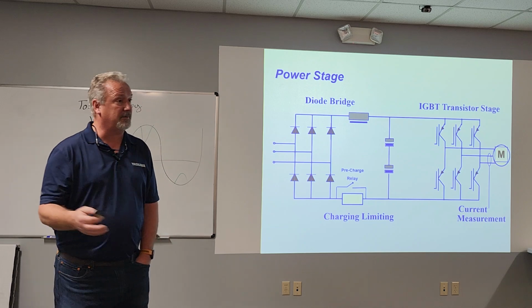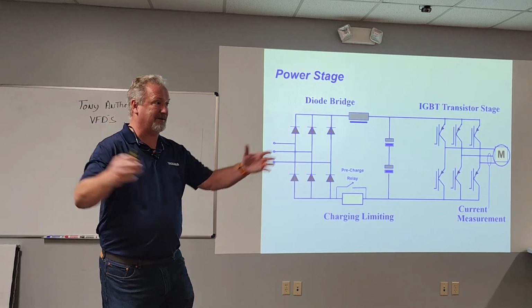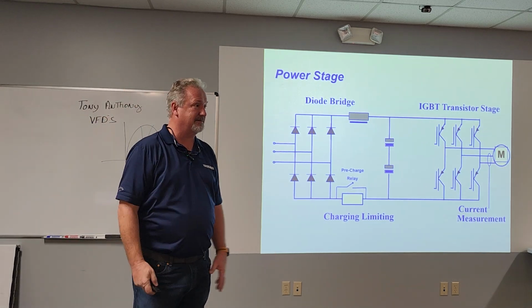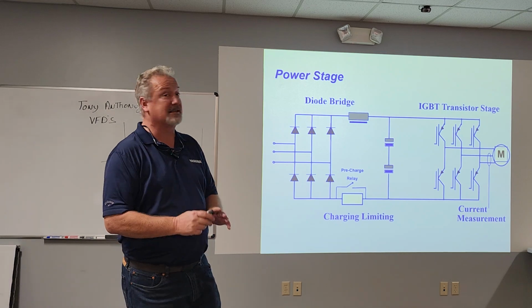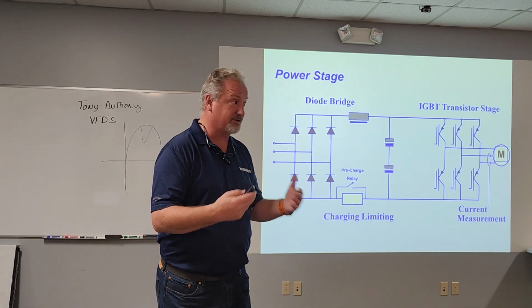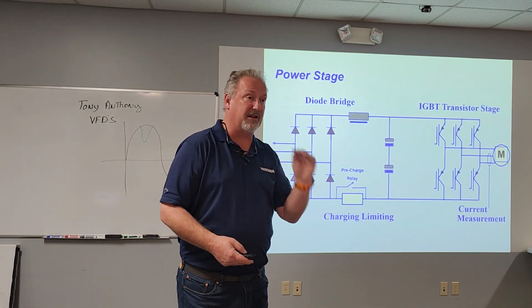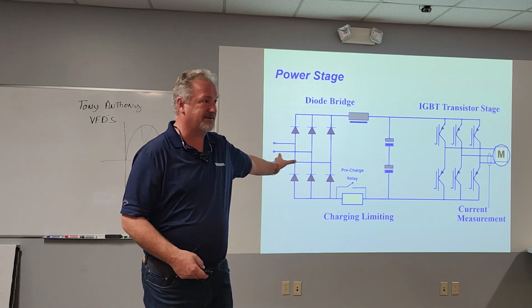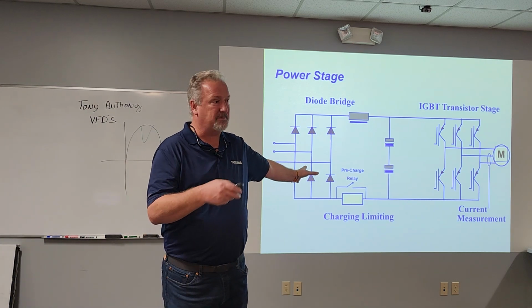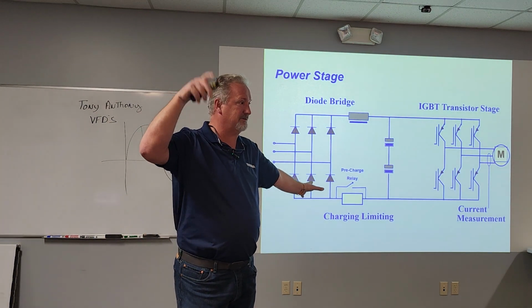The old rule of thumb that we used to use back in the day when drives were big and they had extra capacitance was 2-to-1. That is no longer the case. Some people out there still will try to do that. You literally do not size your drives at 2-to-1 if you got a single phase input because you may run out of power when you get up around 60 hertz.